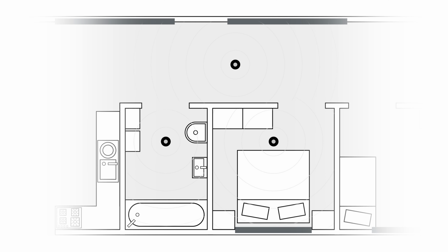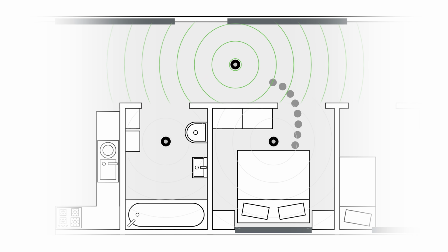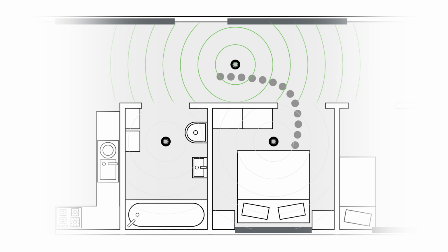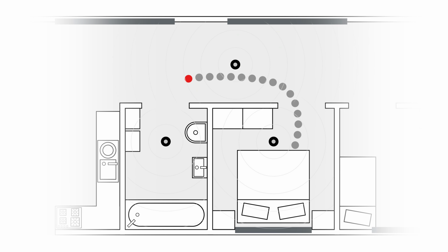Let's start with the fall control. The fall control triggers an alarm chain as soon as there is a fall from which you cannot recover on your own. The principle behind it works like this. If a resident gets out of bed at night to go to the toilet, for example, the presence detector in the bedroom detects the movement and a follow-up time begins in which further movement must be detected before the alarm starts. If the person now walks down the hall towards the bathroom, the next presence is detected here and a new run-on time begins. If the person falls down and stops moving within the range of the presence detector in the bathroom, an alarm is triggered after the defined run-on time.